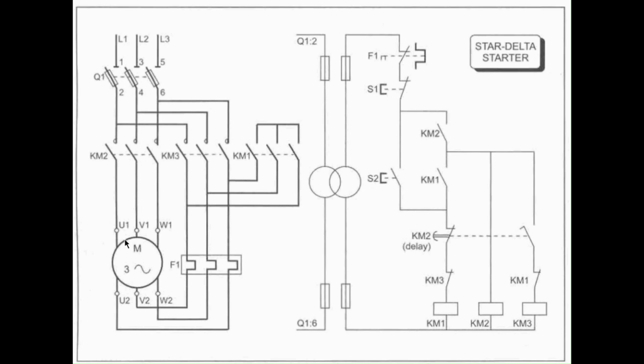What we see now is the motor is connected in star configuration. This is the start point. Now after a delay, we have a changeover. So KM1 will open and KM3 will close. This is denoted here. This shows a mechanical link. When this opens, this closes, and then KM3 will come in. And then the motor will be operating in delta.